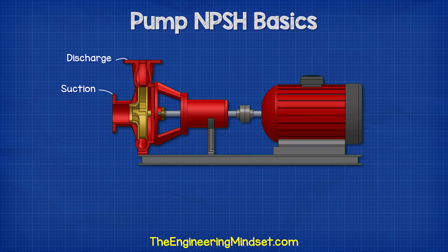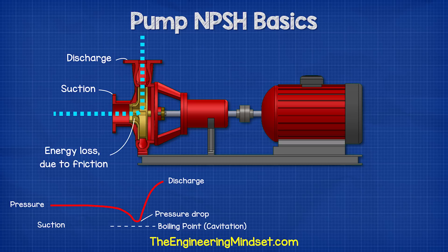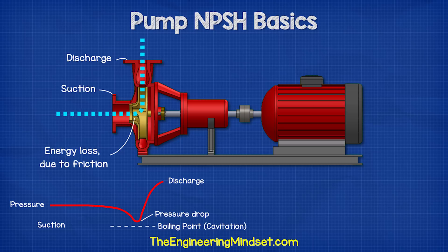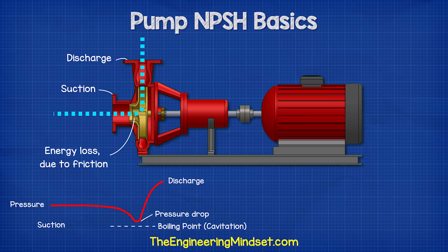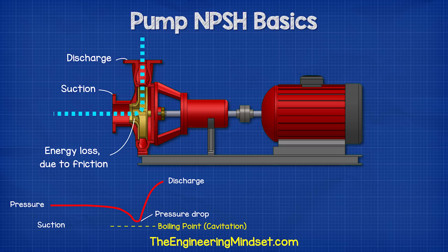The NPSHr value is basically a warning or danger point. As the water enters the pump and flows into the impeller's eye, it loses a lot of energy due to friction. This will give us a pressure drop. At certain conditions, the water flowing through this section can reach boiling point — when this occurs, we refer to this as cavitation.